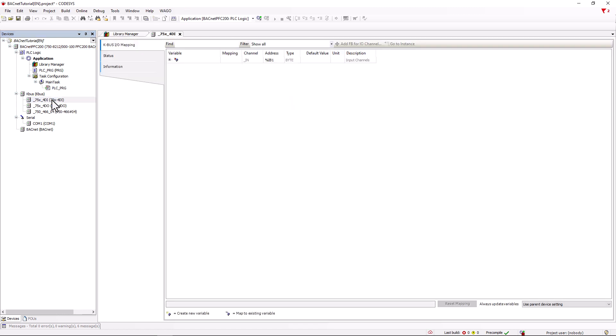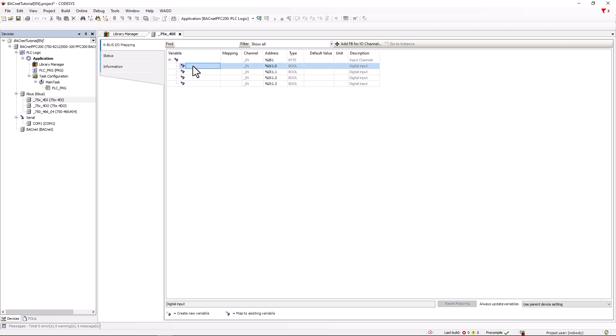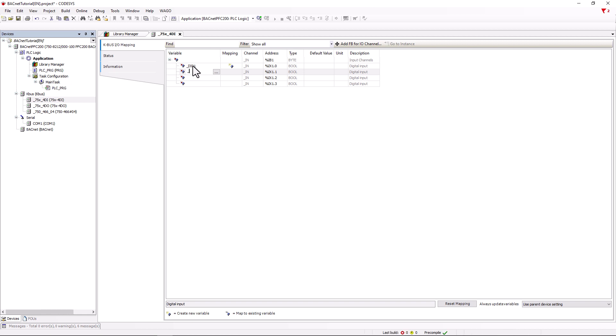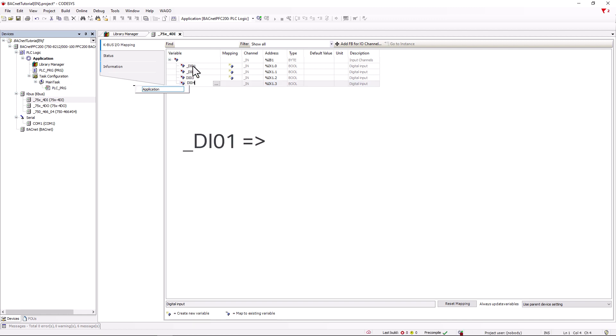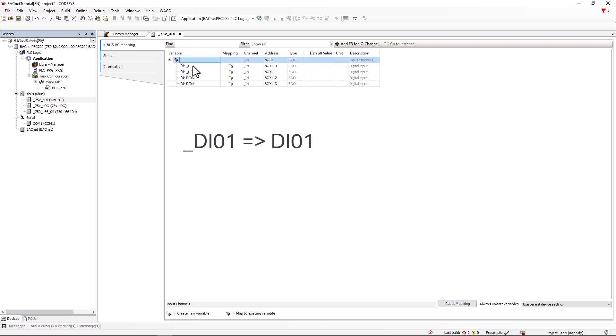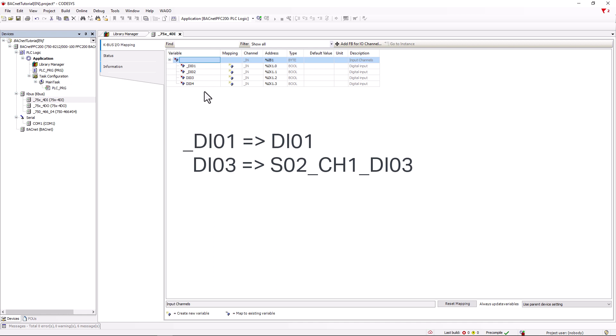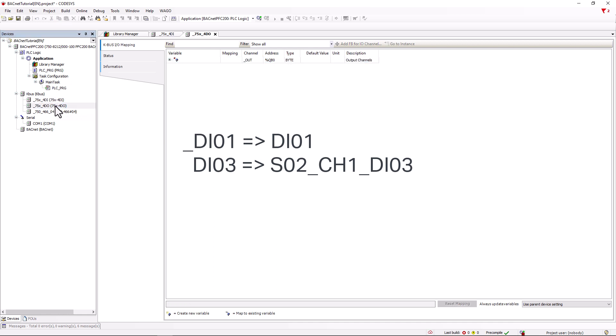By double-clicking on one of the modules, we have the possibility to give the channels names. It's important that the names are IEC 61131 compliant. These names are used by the BACnet configurator as object names for the native BACnet objects — the objects that are automatically generated with a direct reference to an input or output. If the name starts with an underscore, it will be used in the configurator as an object name without the underscore. If no underscore is used, the configurator inserts the slot and channel numbering as a prefix, followed by the assigned name.